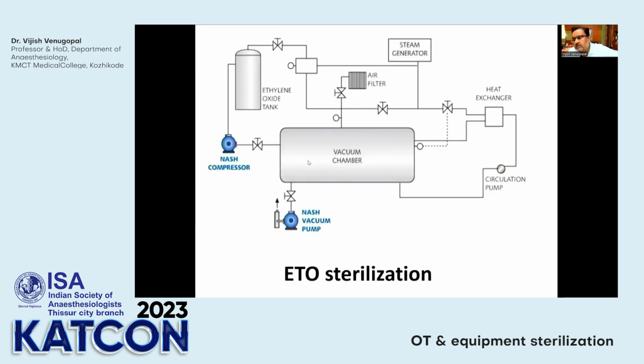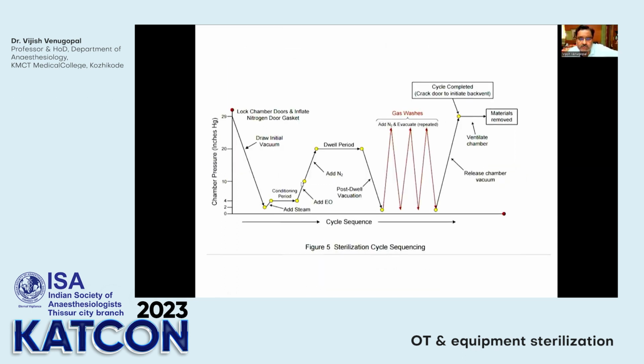This is just the schematic representation of an ETO machine. So what it does is initially it draws in a vacuum, and then you add steam to increase the temperature, and then you have a conditioning period. At the end of the conditioning period, the ETO cartridge opens up, and ETO is added into the system, and then you have a dwell period. So this is the period when sterilization takes place, and this takes place within the first 3 to 4 hours, and then you have the post-dwell evacuation.